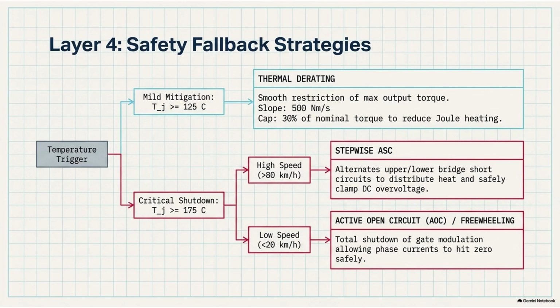That precision mandate extends to the smallest, seemingly most insignificant components on the board. Look at the analog front end, the AFE RC filters. These are the tiny components that process the analog voltage signal coming from the physical NTC temperature sensors before they hit the computer. Remember, this entire circuit board operates inside an enclosure regularly reaching 150 degrees Celsius. Heat doesn't just melt things, it changes their fundamental electrical properties.